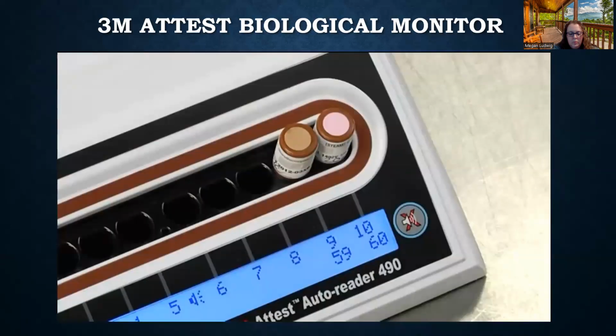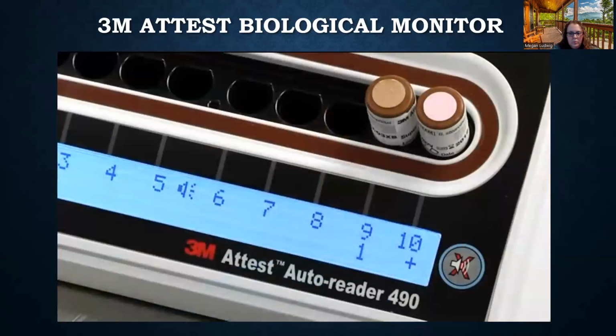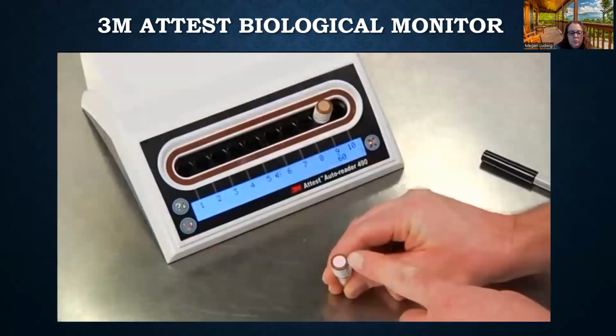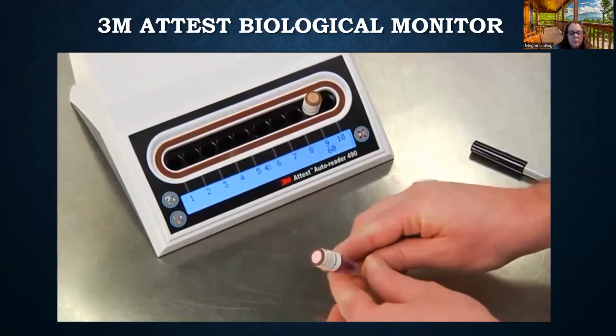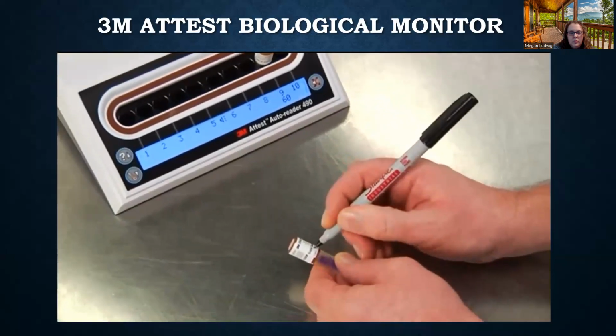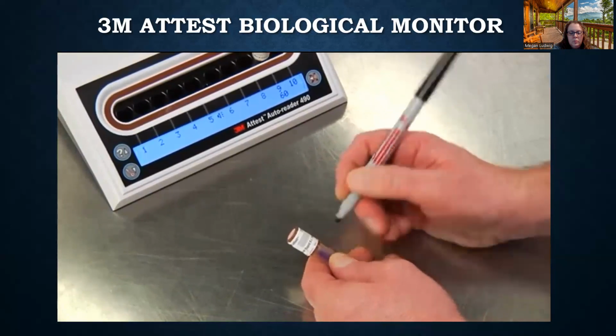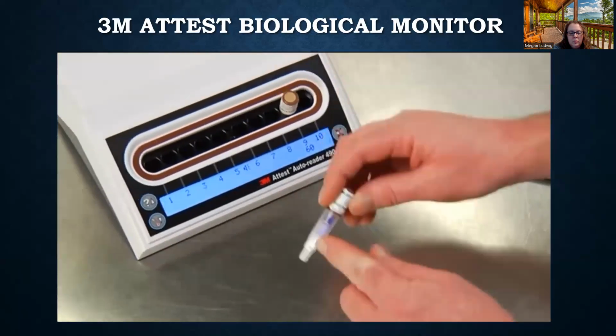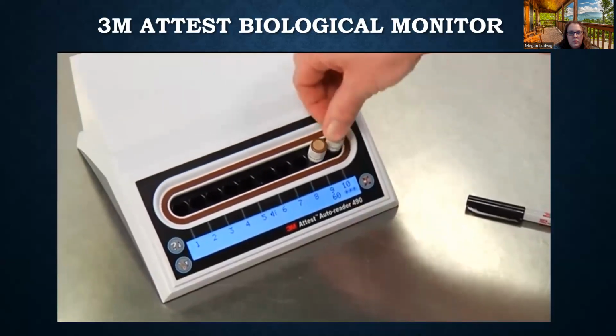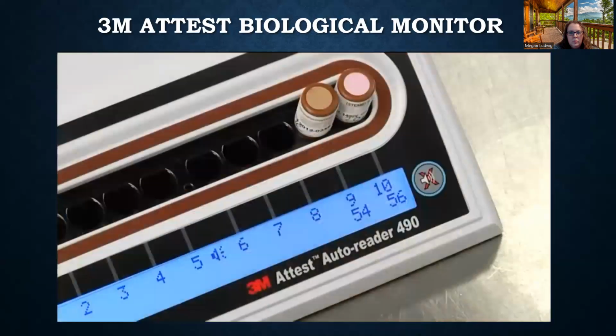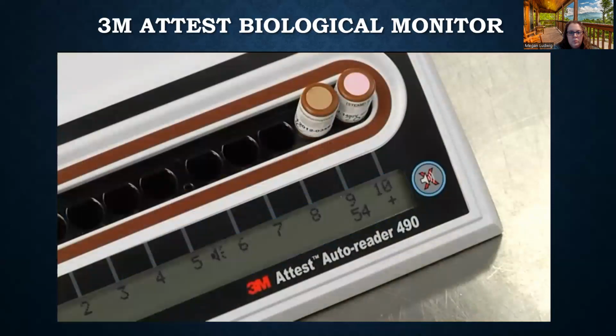A negative result, which indicates a successful sterilization process, will only appear at the end of the full incubation period. At the end of the 1-hour incubation time for 1492 VBIs, if a negative result is detected, you will see a minus sign on the LCD panel directly under the BI. Each day that a processed 1492 VBI is incubated, activate and incubate an unprocessed 1492 VBI as a positive control. The positive control should be from the same lot code as the processed biological indicator. The positive control BI should provide a positive fluorescent result.